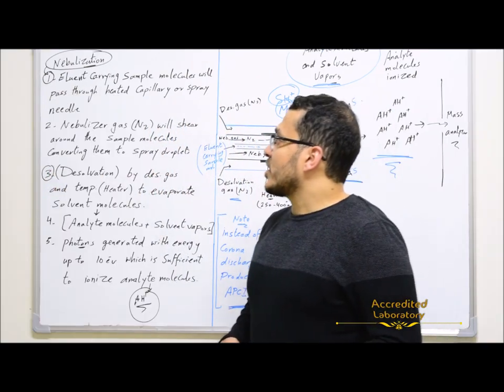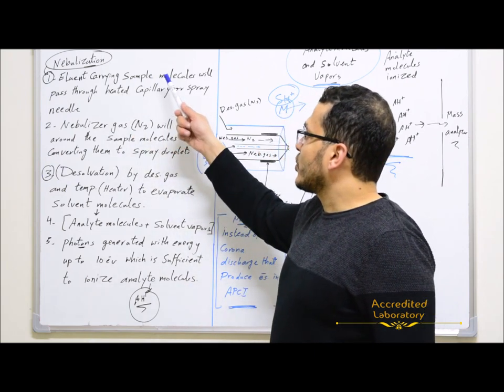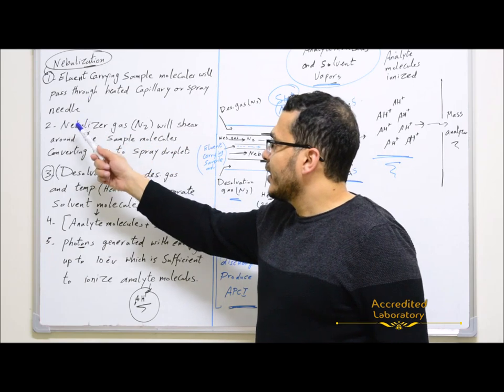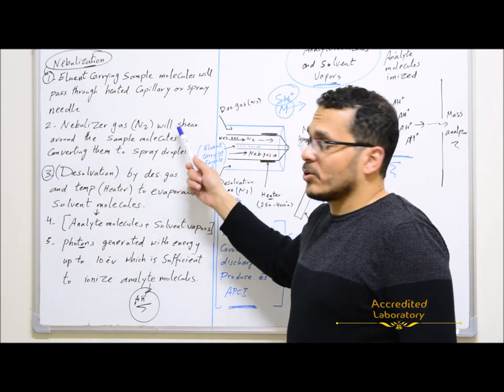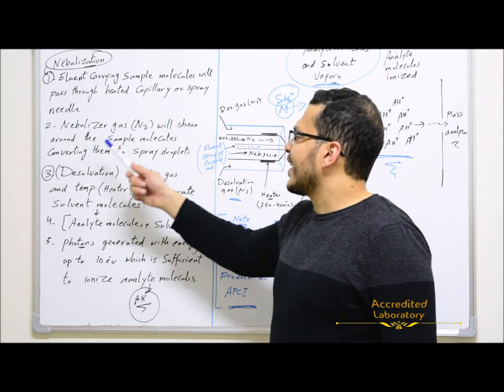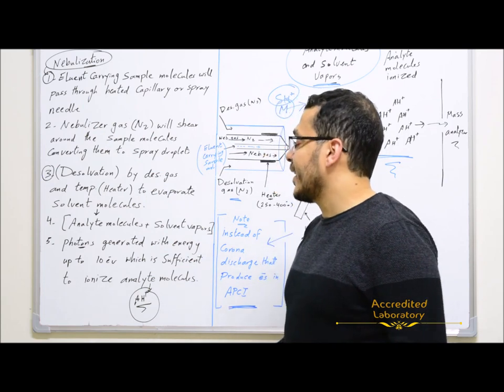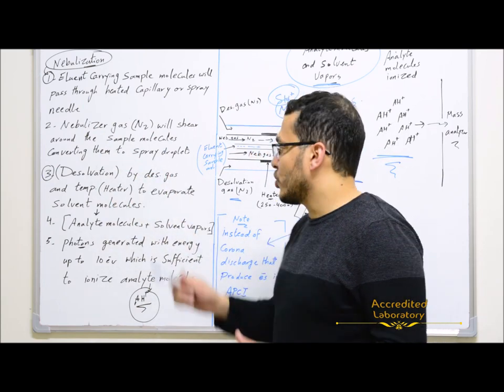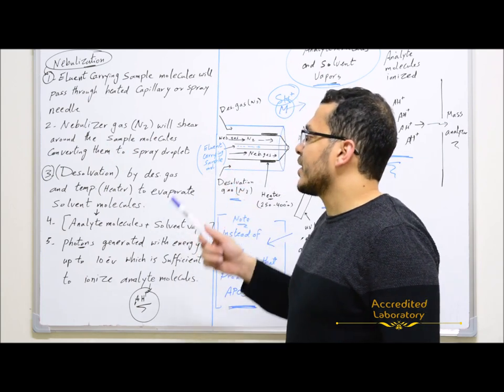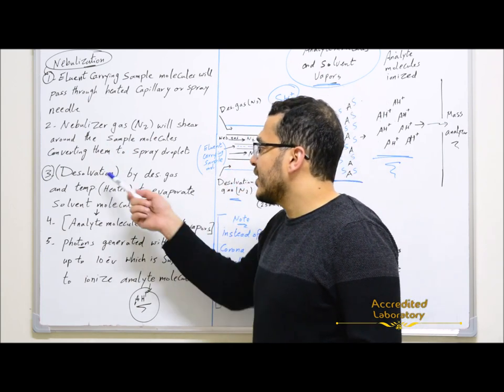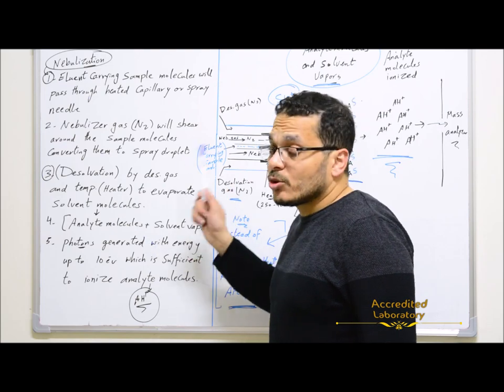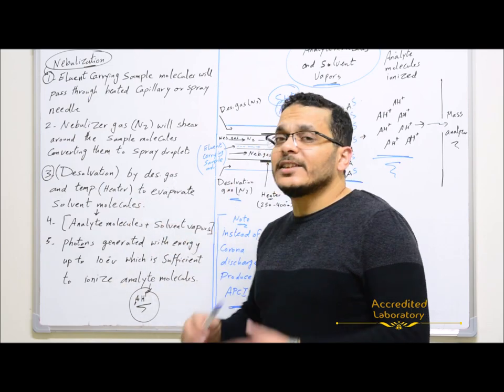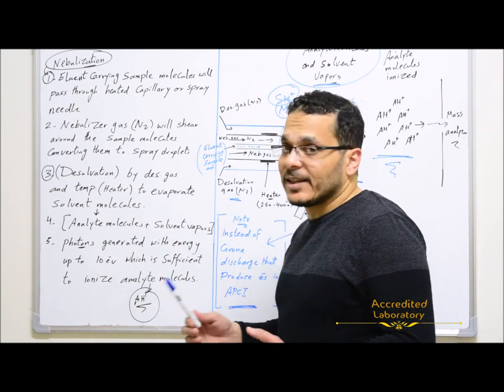In that process, the eluent carrying sample molecules will pass through the heated capillary or spray needle. Then the nebulizer gas, which is nitrogen, shears around the eluent carrying sample molecules, converting them to spray droplets which consist of sample molecules surrounded by the solvent molecules. Then the desolvation process, using desolvation gas and temperature from the heater, evaporates the solvent molecules to get the analyte molecules.